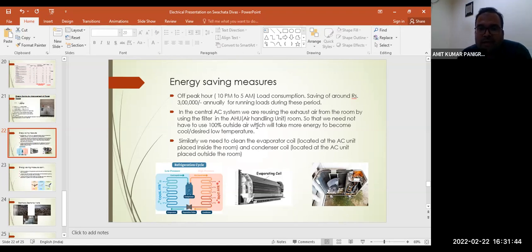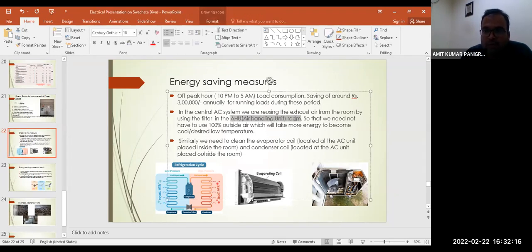And another way how we are saving energy is in the central AC system, which is in all the academic buildings where central AC system is used. In one room, there are two types of ventilation, means ventilation of air, as you can see. One is the fresh air, it goes inside the room, and the exhaust air comes outside the room. That exhaust air we are taking outside the room, and it is going to an air handling unit room. In every floor of an academic building, there is an air handling unit room. There the AHU is filtering the exhaust air which it has taken from the room, keeping its temperature low, and sending it back to our room as fresh air.